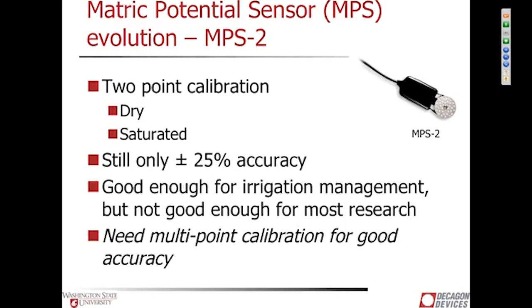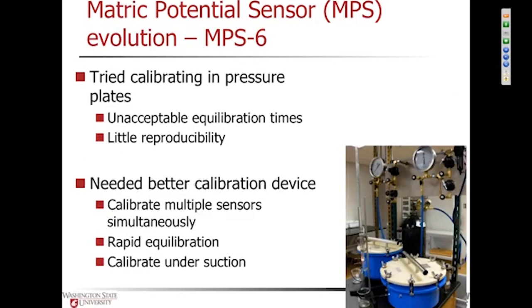But when we were evaluating this, we figured out that to get research grade accuracy, we need a multi-point calibration for good accuracy. And we originally started trying to do a multi-point calibration in the pressure plates, and I would classify that as a failure. The equilibration times in pressure plates are ridiculously long, talking about leaving sensors in there for several weeks to come into equilibrium at multiple points, and the reproducibility was horrible. And we've spent a little bit of time looking at the problems that went on there, and the problems with equilibrating soil under positive pressure instead of suction are pretty well chronicled in the literature. And so we're pretty well convinced that the pressure plates are not a good way to calibrate these instruments.